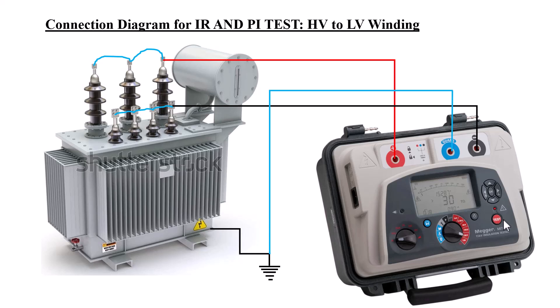For our test, we will select the knob to 5 kV. This is the test button — when we press it, the test will start after two seconds. The mode selection knob offers different test options. The first is insulation resistance; the second is IR with timing, which works for one minute. We will select the second option, and after that we will start our test. The set will inject 5 kV.